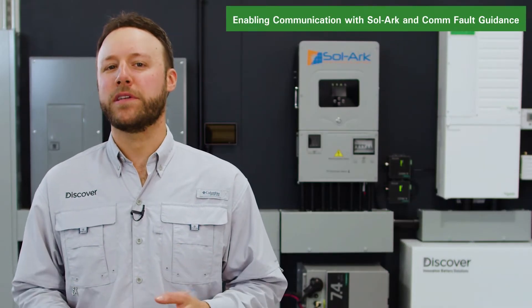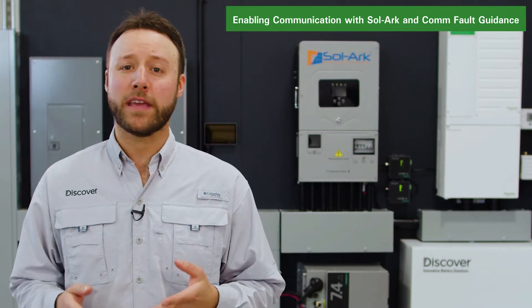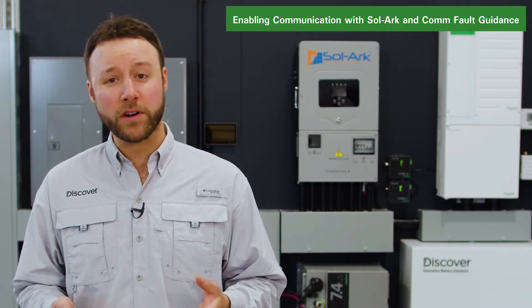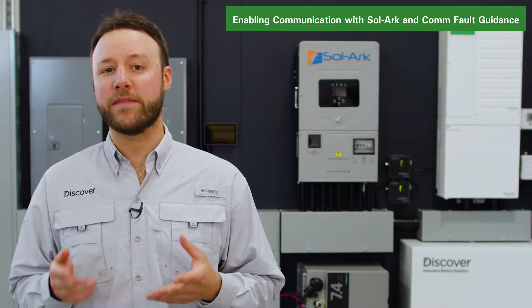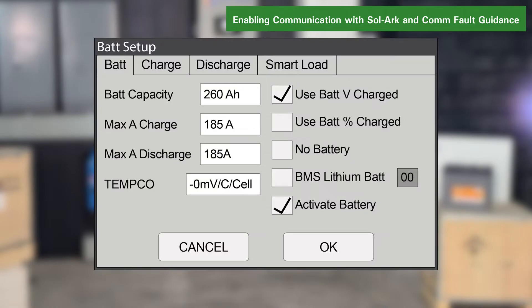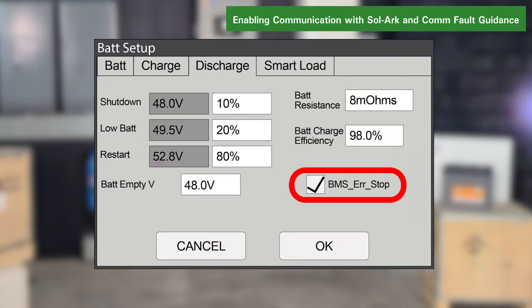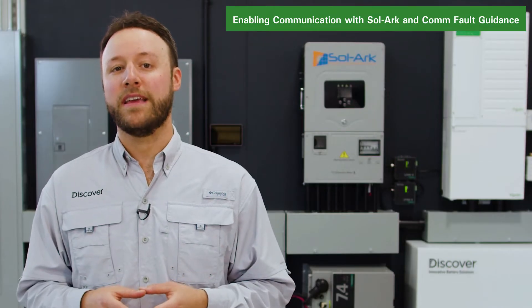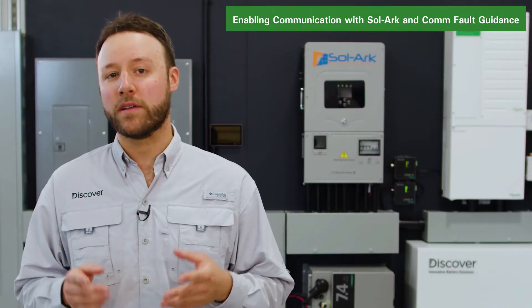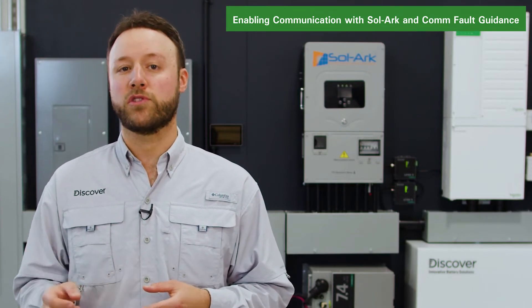Now that the hardware is installed, you can enable LINK2 to communicate with Sol-Ark inverters. Be aware that if communication between the LINK2 and the inverter is lost for more than 10 seconds, the inverter will safely stop operation only if the inverter's BMS lithium BAT and BMS error stop parameters are both enabled. If closed-loop communication can't be re-established, the Sol-Ark inverter must be changed to an open-loop configuration to resume operation.